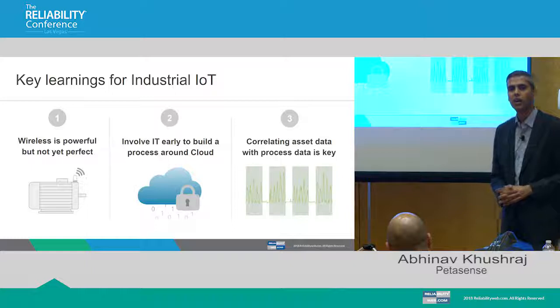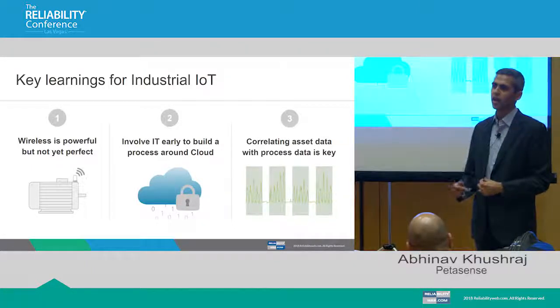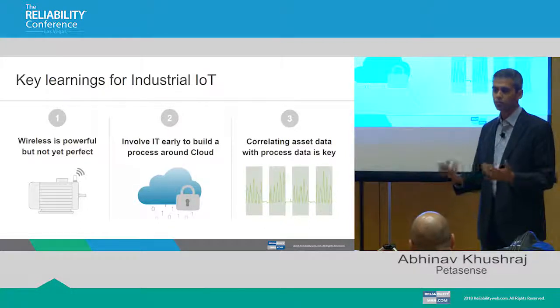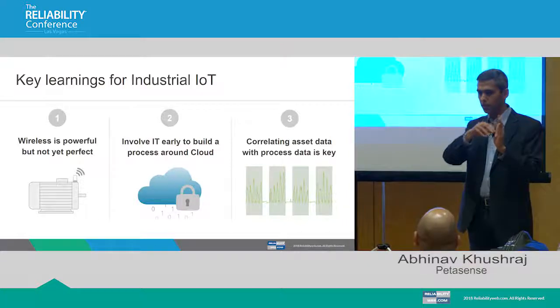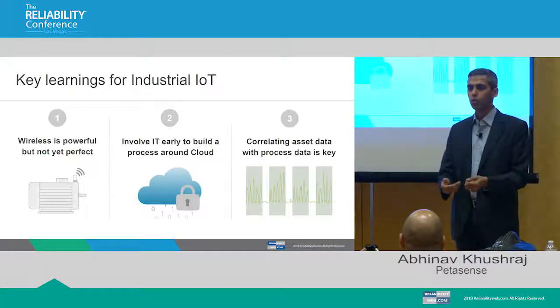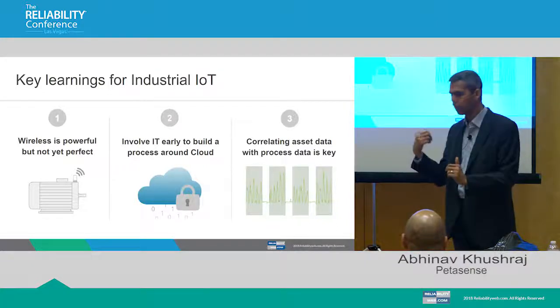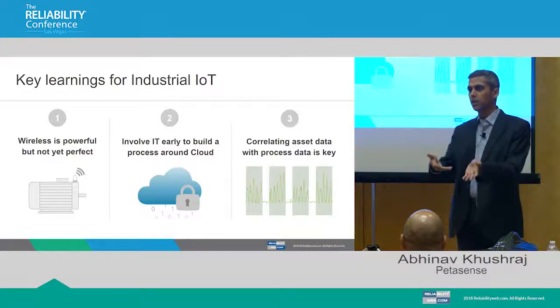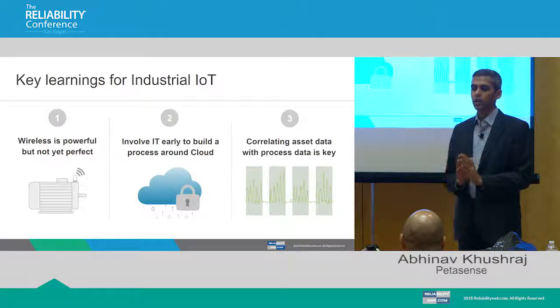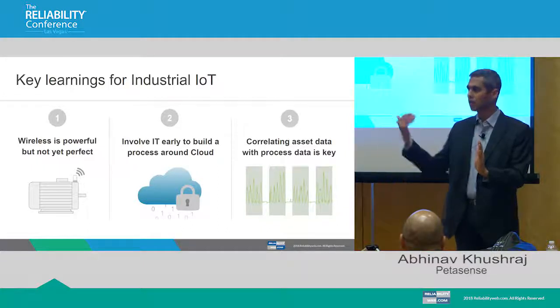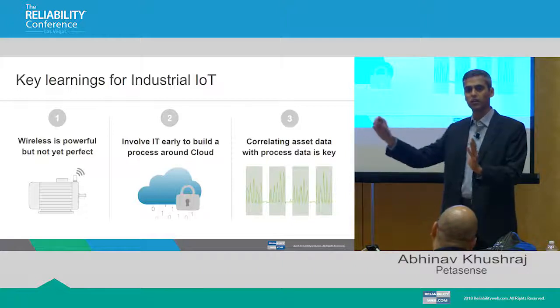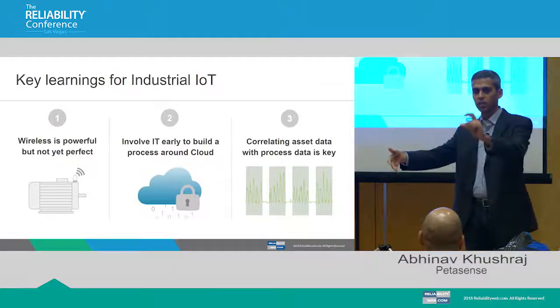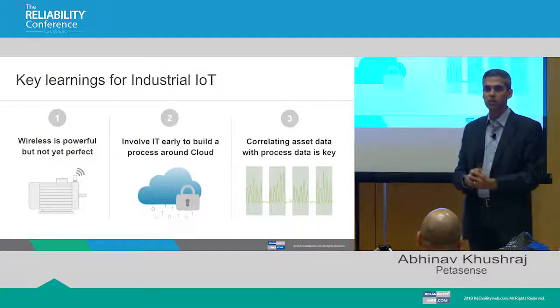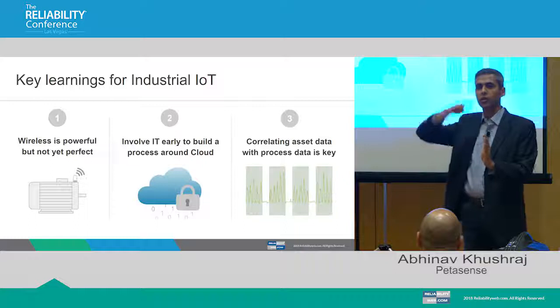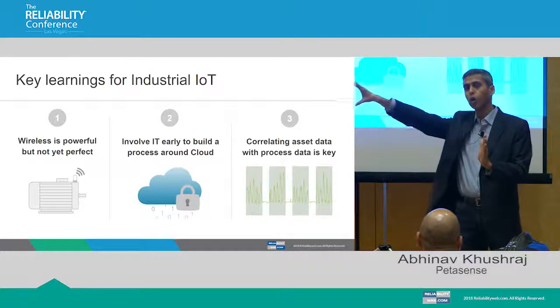Can you define what a tag is? A tag comes from a triaxial sensor that also has a temperature sensor. Each vibration axis gives you raw vibration data, a waveform. That waveform can be converted to a spectrum. From the waveform you can compute average vibration, peak to peak, all of that is a tag. If you collect a waveform every 3 hours, it gives you an average RMS, so you get 8 RMS values per day. You get a trend of the RMS, the peak, and the crest factor. Those are the broadband tags from the waveform.